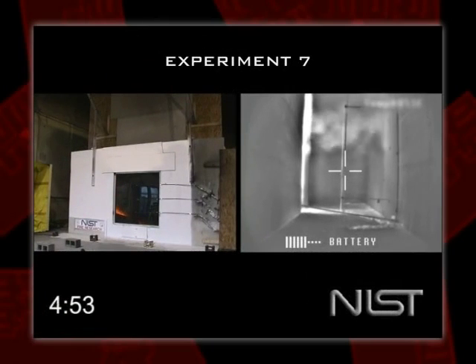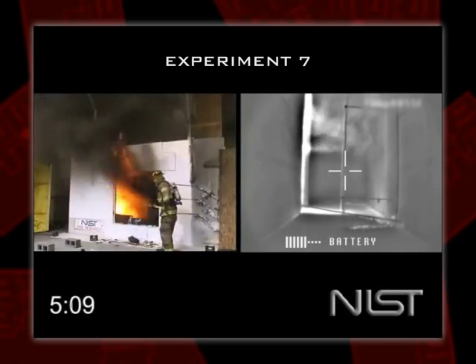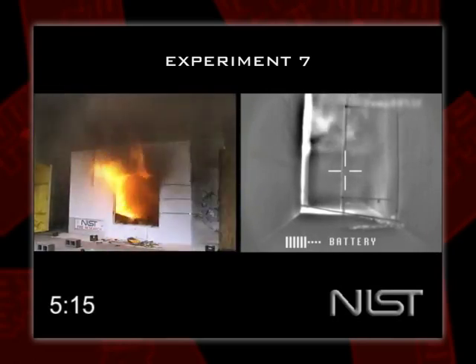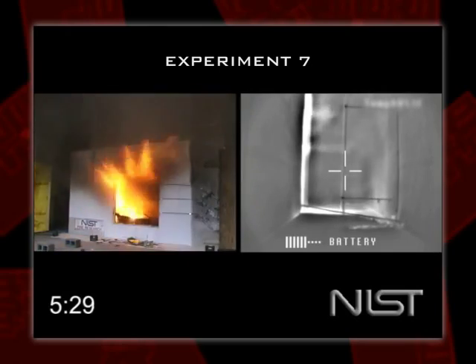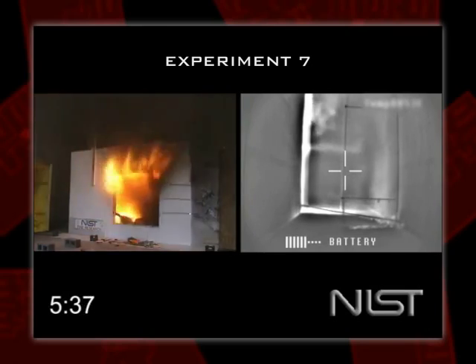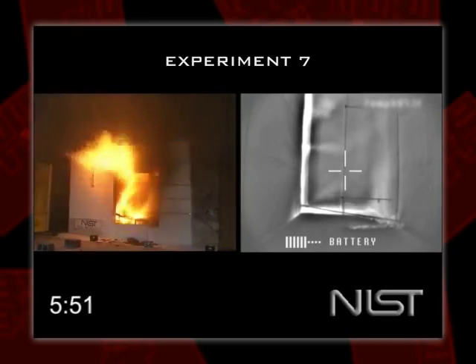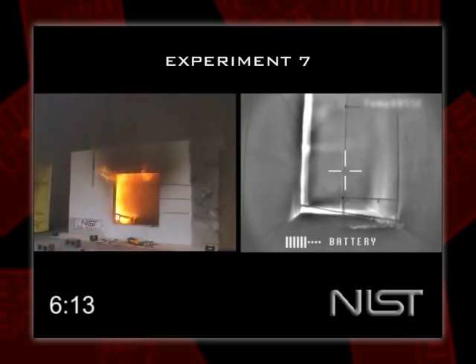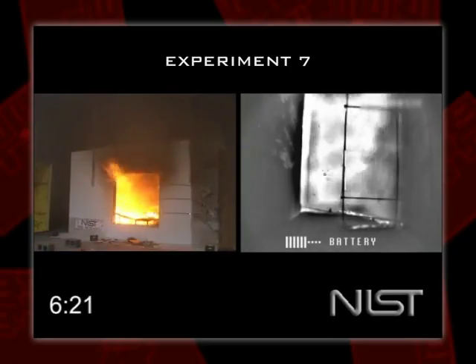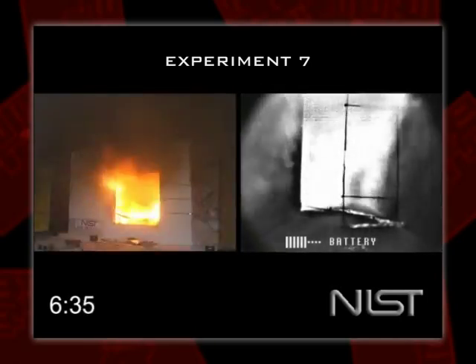Here's test seven. The fire is building and we fail the window, but the door to the corridor is closed. What you see are leaks around the door, a small opening at the keyhole, and hot gas being pushed under and around the door. We still have flames blown back out. We let this happen for a while, then we open the door. Don't just go opening doors, or if you open them, only open them a little bit, especially on a windy night. Open the door fully — boom. Untenable conditions in the corridor within seconds — a very dramatic change. Door control is very, very important.